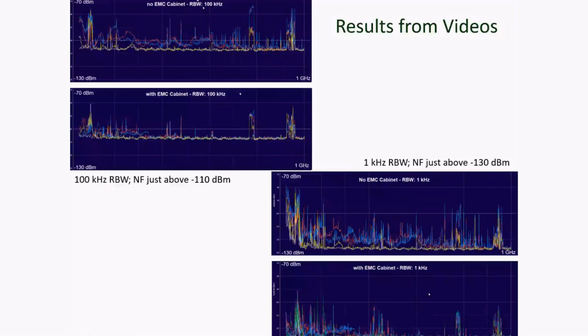Just to increase the resolution, we change from 100 kilohertz to 1 kilohertz, and you'll see the noise floor of the yellow trace drops down to nearly minus 130 dBm. When I was a kid, if I could have had spectrum analyzers of that performance, it would have been revolutionary. We've come to expect it of modern spectrum analyzers. The trouble is, if you want to measure down to those levels of sensitivity, you cannot have your spectrum analyzer exposed. You need to put it into a cabinet.